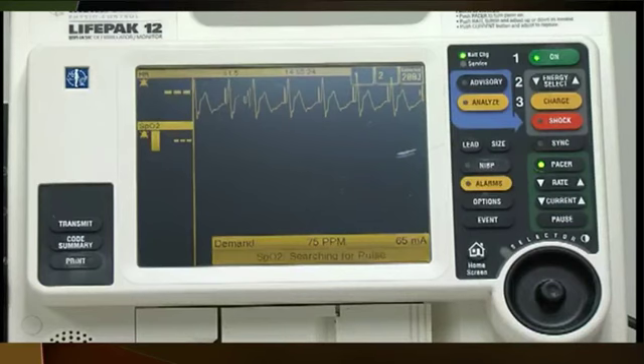So the video is actually of a LifePak 12, which is very similar to our LifePak 20. If you look at this defibrillator, the buttons are exactly the same. Our dial's not that big. So in order to turn the pacer on, first you would turn the unit on, which is that green button at the very top. And if you look on the actual device, you can see a green box at the bottom.